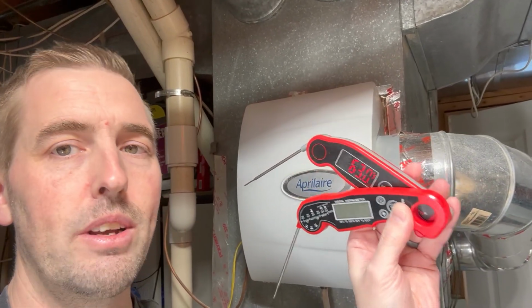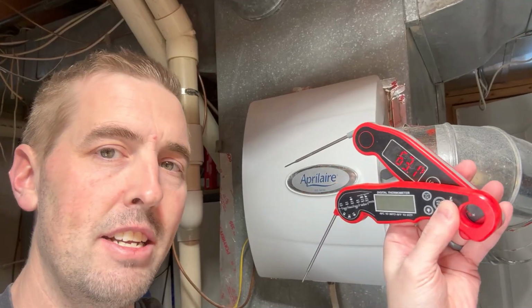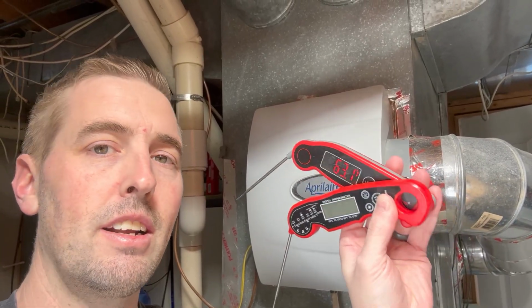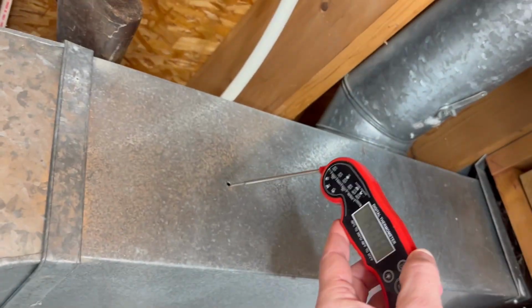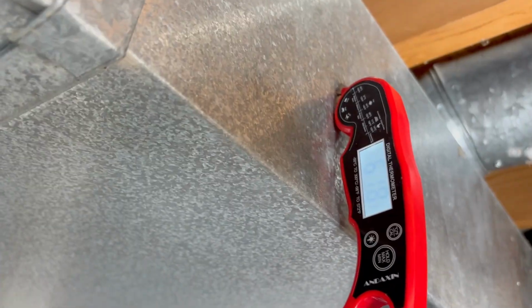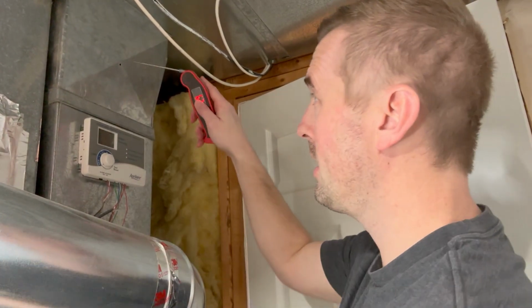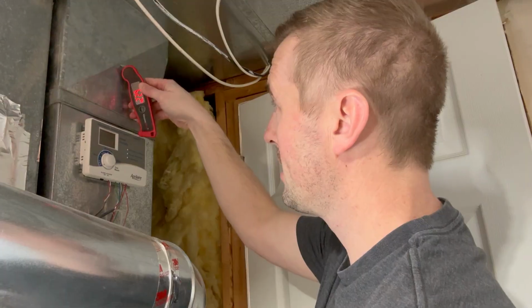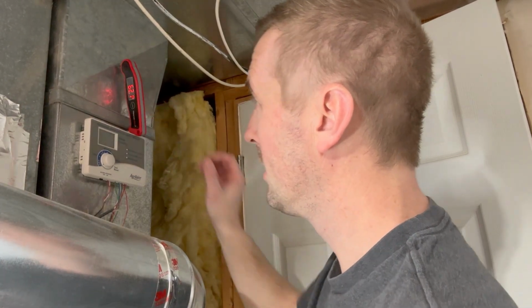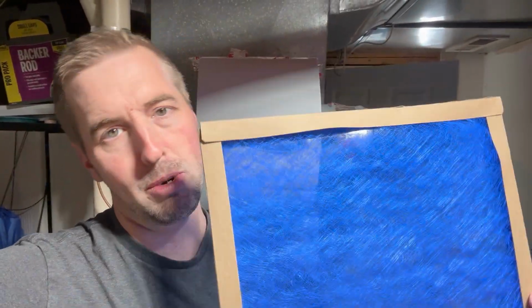So what we're going to do is use these thermometers to gauge kind of the impact of each filter on the delta. So with one of our thermometers, we'll be positioning it here in this hole on our supply ductwork. We'll just let it hang there, and then we can grab the reading as we switch out each filter. And then on the return side, got a hole in this duct. Just go ahead and slide the other thermometer in, allow it to dangle, and then we can go ahead and take the reading on the return side. And between the supply and return measurements, we can calculate that delta. And so first up for testing is going to be our MERV 2 fiberglass filter.